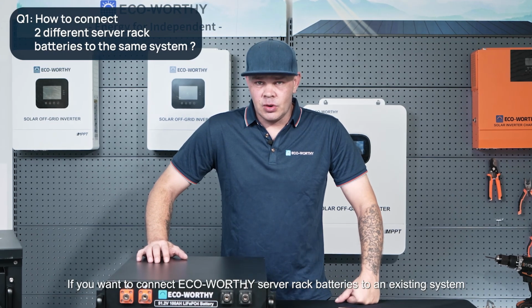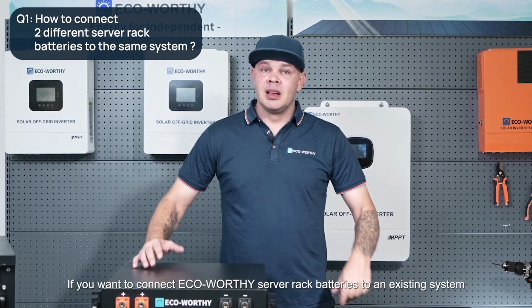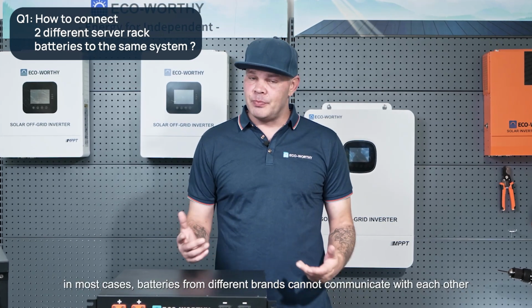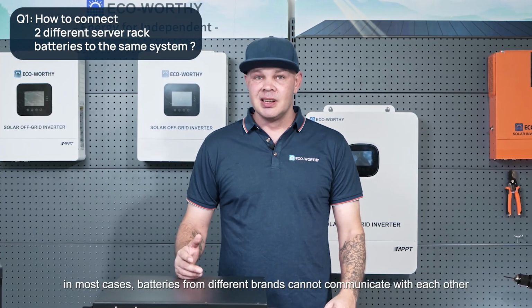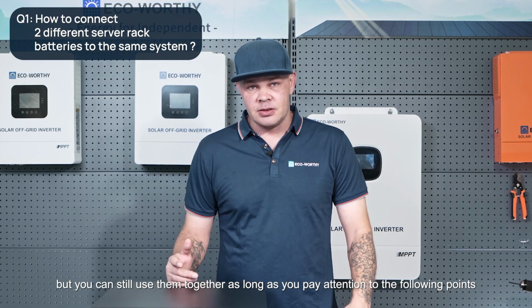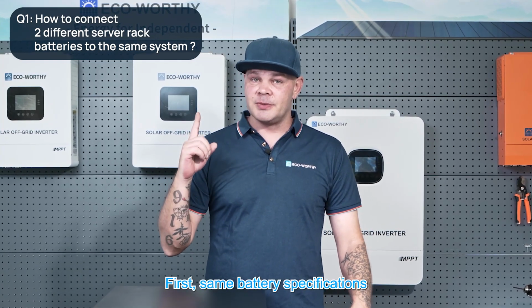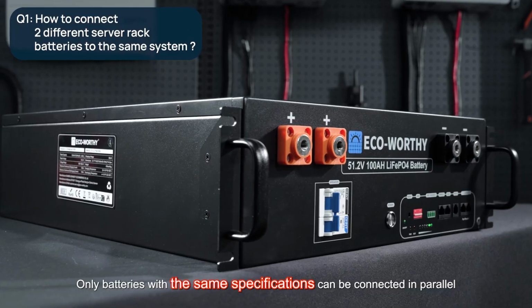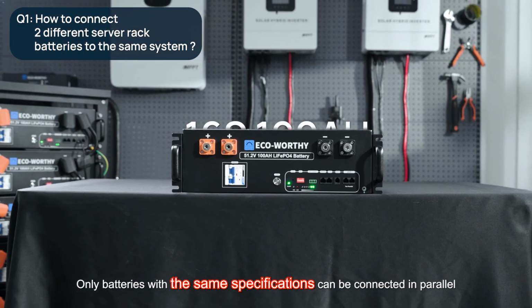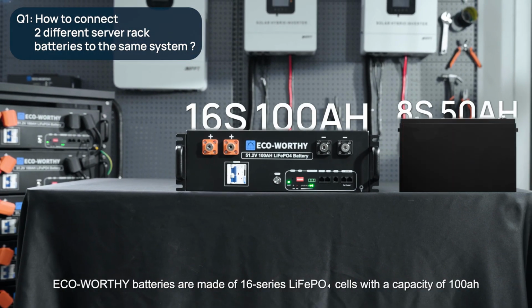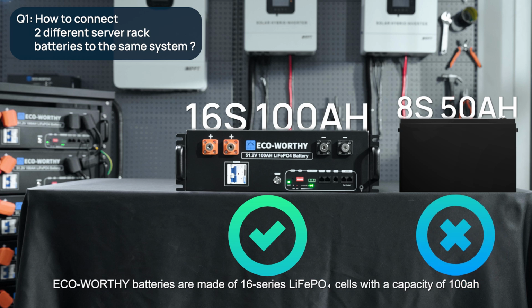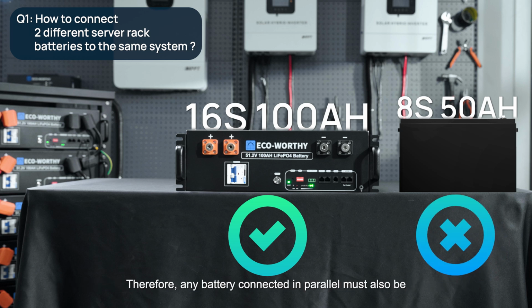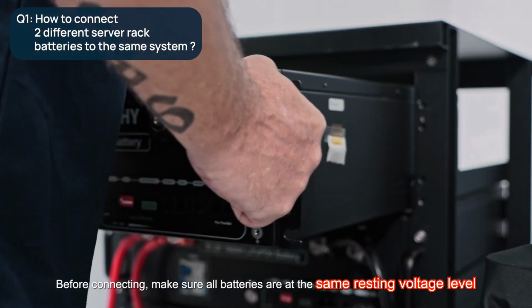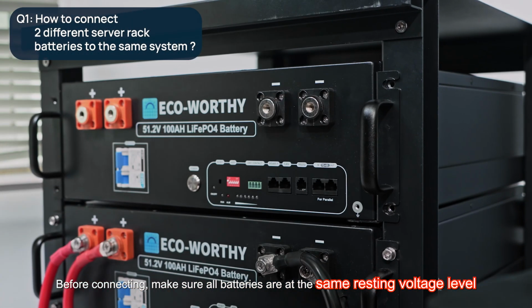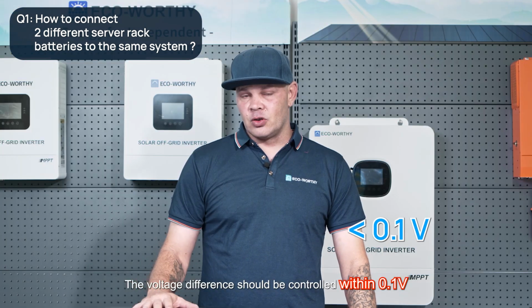If you want to connect eco-worthy server rack batteries to an existing system, here's what you need to know. In most cases, batteries from different brands cannot communicate with each other, but you can still use them together as long as you pay attention to the following points. First, the battery specifications must be the same. Only batteries with the same specifications can be connected in parallel. Eco-worthy batteries are made of 16 series LiFePO4 cells with a capacity of 100 amp hours. Therefore, any battery connected in parallel must also be a 16 series LiFePO4 battery with a capacity of 100 amp hours. Before connecting, make sure all the batteries are at the same resting voltage level. The voltage difference should be within 0.1 volts.